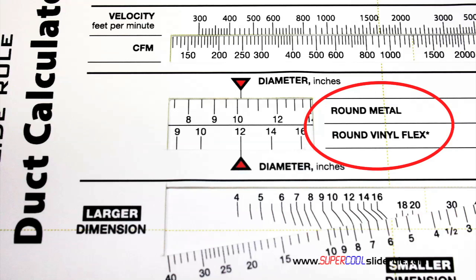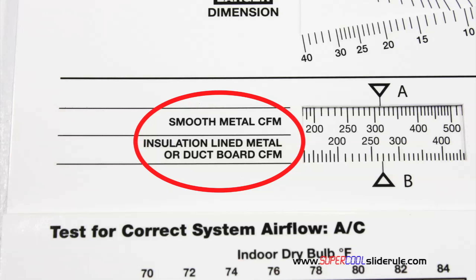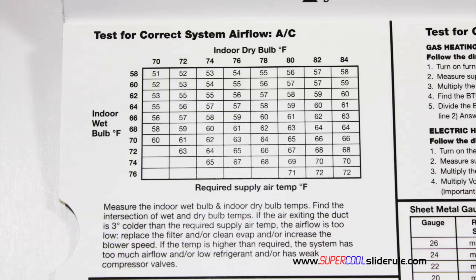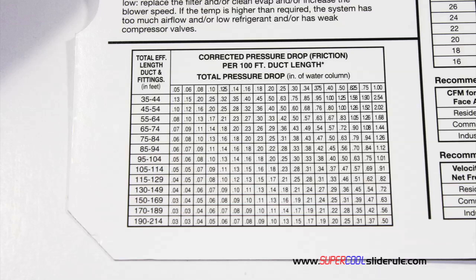Inside is packed with even more information. It performs sizing of both metal and flexible duct, and has the only direct reading conversion from smooth metal to insulation-lined metal we've ever seen. The majority of technicians have never been taught that if the insulation is on the inside of the ductwork, you cannot size it with a regular duct calculator. It has step-by-step directions for determining airflow through a gas furnace, electric furnace, or an air conditioning unit, as well as pressure drop multipliers for ductwork and recommended velocities.